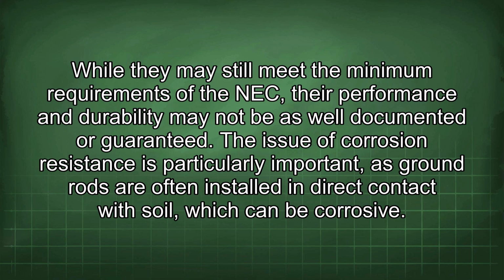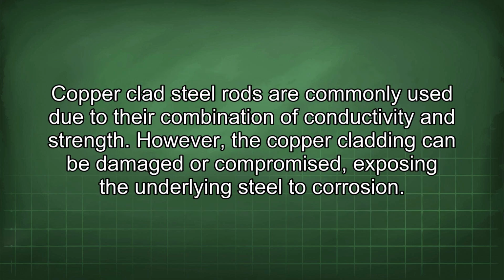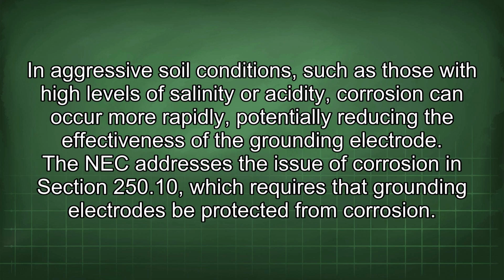documented or guaranteed. The issue of corrosion resistance is particularly important, as ground rods are often installed in direct contact with soil, which can be corrosive. Copper-clad steel rods are commonly used due to their combination of conductivity and strength. However, the copper cladding can be damaged or compromised, exposing the underlying steel to corrosion. In aggressive soil conditions, such as those with high levels of salinity or acidity, corrosion can occur more rapidly, potentially reducing the effectiveness of the grounding electrode.